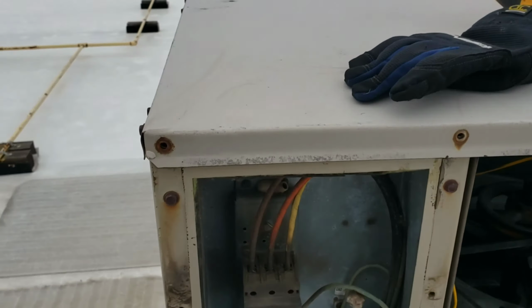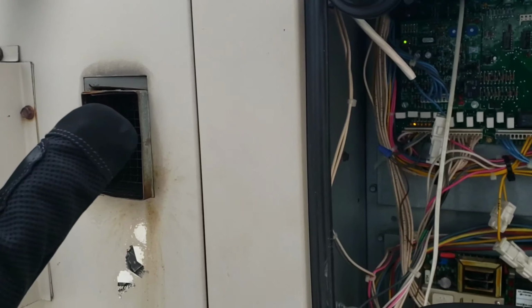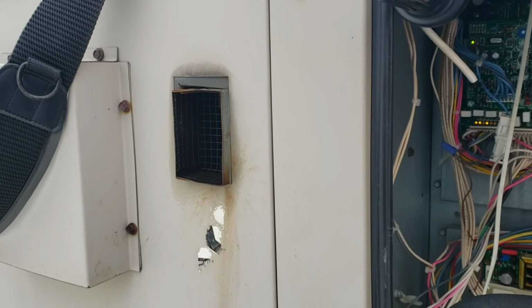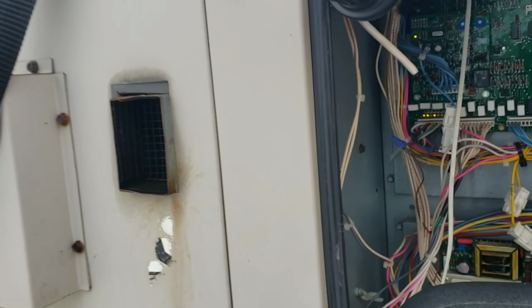All right, here goes nothing. I haven't put any of the doors back on yet, but I want to come over here and see if it lit up, see if we have any codes. I want to see the blower kick on too, but hey, our inducer draft kicked on just like it should, as part of the sequence of operation.